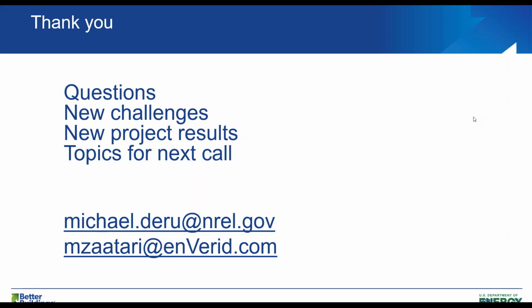Next: when you do regeneration at night, nighttime purge, and thermal mass cooling may not be possible, does this have any implications on energy savings? What we do is a 1 hour regen at very low airflow—only 300 CFM per module during regeneration. I should have mentioned that in the presentation. You're able to schedule the regen to stagger the units, so not all units regen at the same time. If you do it at night, say from 10 to 11, you have ample time to cool the system before it regens again during the day. So there's no concern here. One advantage is that we can stagger the units, so if you have 10 units, you don't have to regen all of them at the same time.